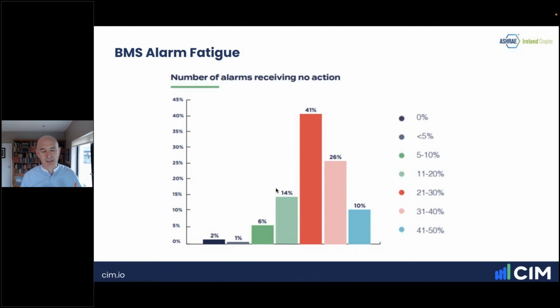Most of the BMSs we see on the sites we work on aren't able to differentiate between the different priorities of alarms. The BMS will know when it's a critical alarm and a piece of plant has stopped, but in terms of identifying opportunities to optimize the plant in advance, to allow energy savings or operational improvements, BMSs just aren't programmed that way. Typically in our experience, the BMS vendors aren't tasked with that scope. Their primary function is to maintain conditions, and doing so in the most energy efficient way isn't necessarily part of their brief. So that was another interesting statistic.